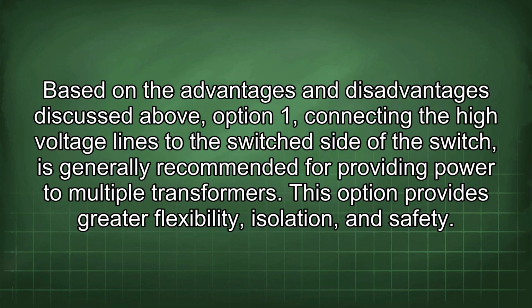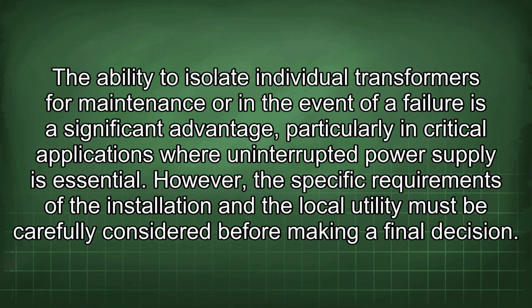Based on the advantages and disadvantages discussed above, Option 1, connecting the high-voltage lines to the switched side of the switch, is generally recommended for providing power to multiple transformers. This option provides greater flexibility, isolation, and safety. The ability to isolate individual transformers for maintenance or in the event of a failure is a significant advantage, particularly in critical applications where uninterrupted power supply is essential. However, the specific requirements of the installation and the local utility must be carefully considered before making a final decision.